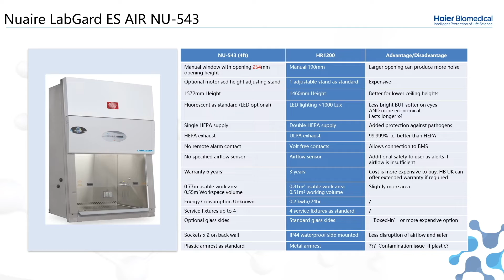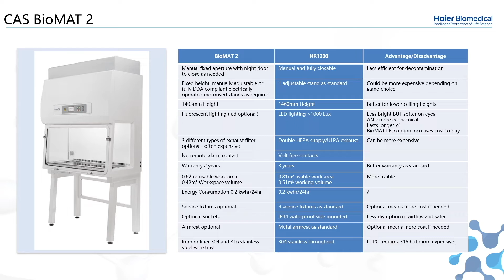The CAS BioMat 2 is also very popular in the UK, and we come up against it quite a lot. The unit is slightly shorter, which provides very good ceiling heights. However, they use fluorescent lighting instead of LED, don't provide volt-free contacts as standard, don't come with a 3-year warranty, and have a smaller usable working space. We provide 4 service fixtures as standard, as well as sockets mounted on the side with IP44 waterproofing, and a metal armrest as standard.